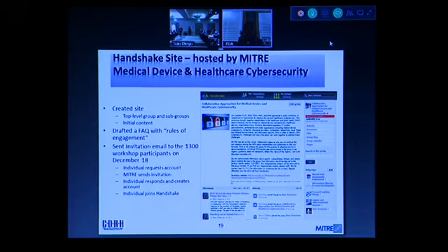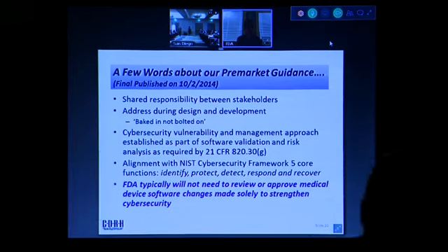So I'd like to now pivot for just a few moments to underscore a few key principles of the final guidance that we issued on October 2nd, 2014. The title of that guidance is Content of Premarket Submissions for Management of Cybersecurity in Medical Devices. Again, FDA recognizes that medical device security is a shared responsibility between stakeholders. That includes healthcare facilities, patients, providers, and medical device manufacturers. Cybersecurity should be addressed during design and development. Again, that very concept of let's bake cybersecurity in, not bolt it on, which is a problem that we actually face today with many of the legacy devices.